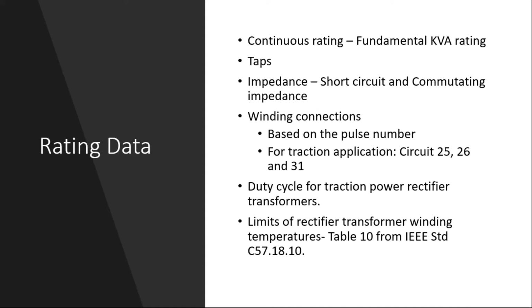And next we have a commutating impedance. For the commutating impedance, just one winding is in the rectifier circuit, the other is shorted, and the impedance is calculated or tested for that condition. And this is very important for rectifiers when the current changes from one diode combination to the next one. So that is very important.